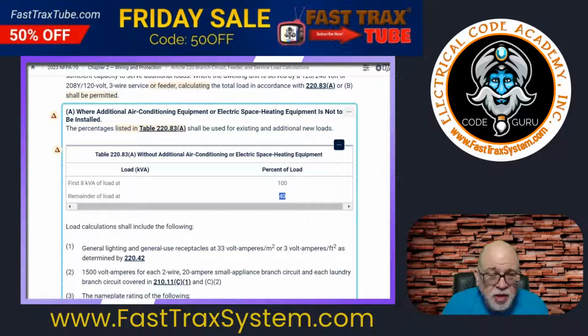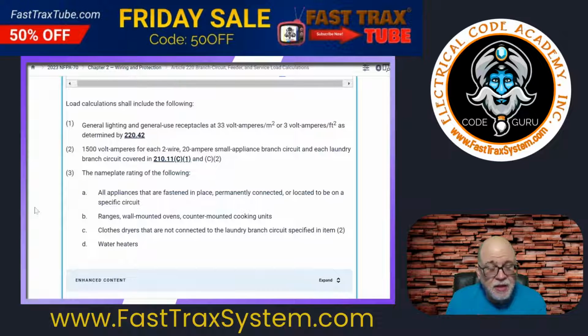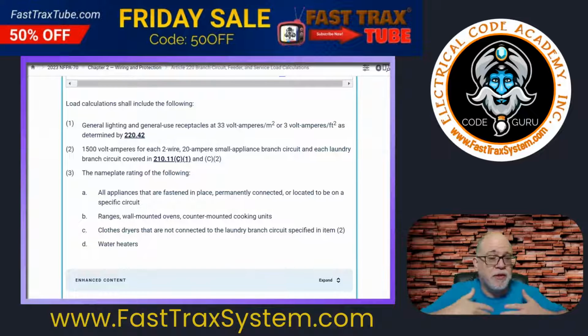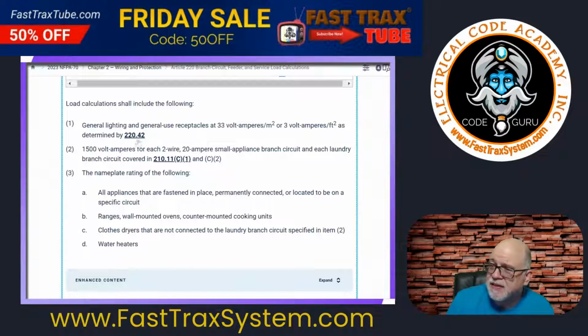This is pretty similar to what you get when you do the optional method for a single dwelling, right? The only difference is here it's the first 8,000, whereas in the optional method, it's the first 10,000 and then the remainder at 40%. But here it's the first 8 at 100%. So that's really the only significant difference there. Now, when you're looking at that dwelling, it's existing or not. This is why I talked about at the beginning, maybe you just do a full calculation and see what it would be as if you were building this house new. But it's kind of the same concept.